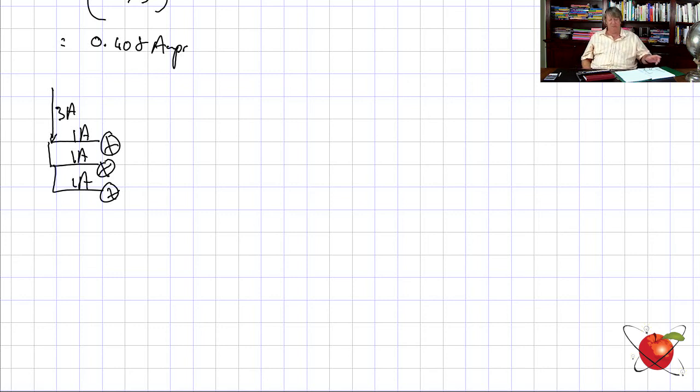What's that amp going to do? Boom. The current is too much. The maximum current is 0.408 amps that we've calculated there. That was the power rating. So that's all it can be. So our next step is to say, okie dokie then. Now we've got a bit of a problem.